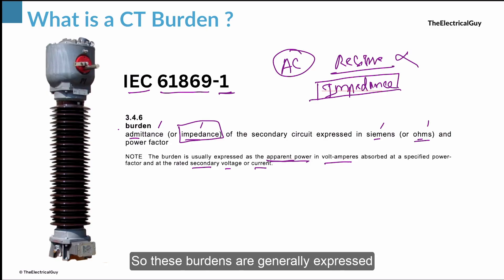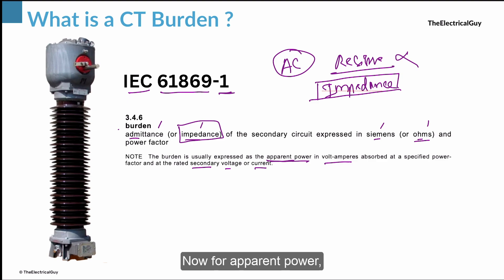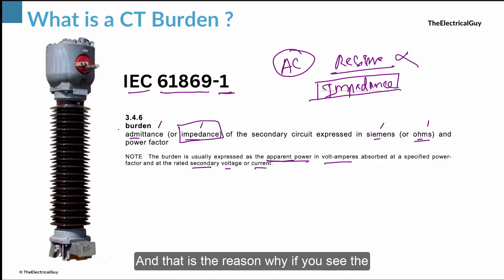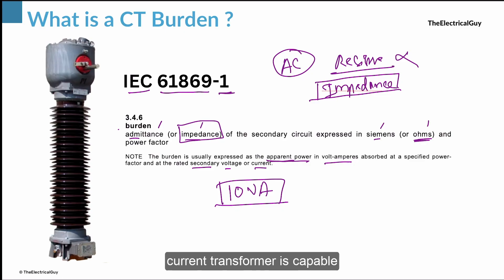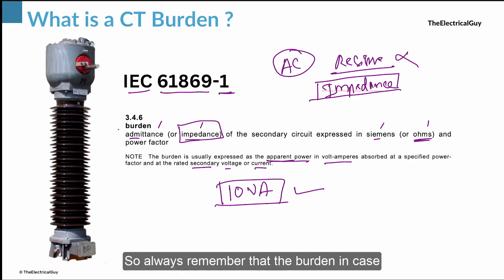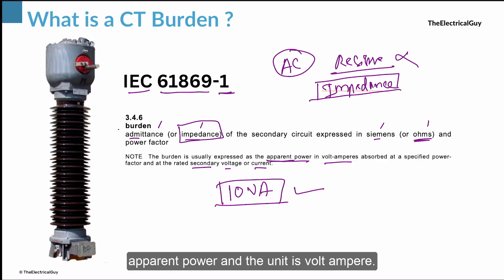These burdens are generally expressed as apparent power in volt-amperes. The unit for apparent power is VA, and that is why if you see the nameplate of a current transformer you will find something like '10 VA' written on it. That indicates that this particular current transformer is capable of delivering 10 VA. Always remember that burden in the case of instrument transformers is referred to by the apparent power and the unit is volt-ampere.